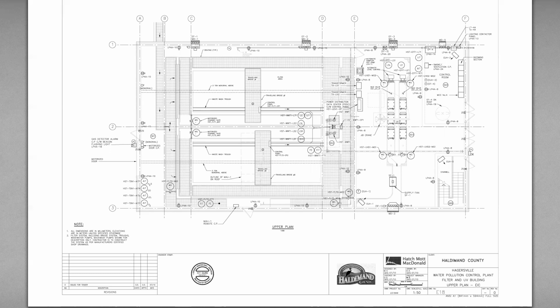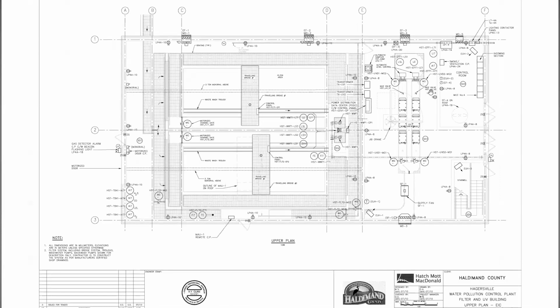If you're specifying that type of equipment, and you could very well be, if you're the one who's designing and deploying the software, the control scheme, you're being paid to deliver an automation system, and you have to spec all the parts, you need to be cognizant of where those parts are going to be. And then if you're reviewing these drawings, if you work for an engineering firm and see where some of these things are being installed, well, you might need to pick up that you don't want to install, this is a heater, the thermometer right across from it.